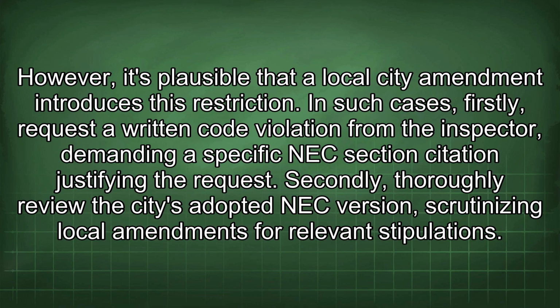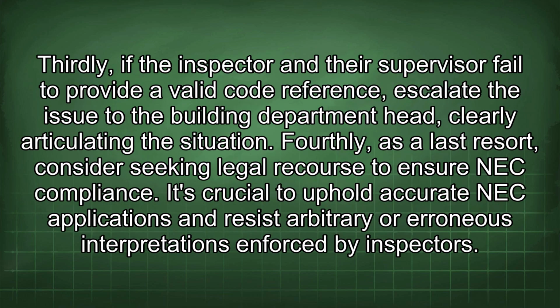In such cases, firstly, request a written code violation from the inspector, demanding a specific NEC section citation justifying the request. Secondly, thoroughly review the city's adopted NEC version, scrutinizing local amendments for relevant stipulations. Thirdly, if the inspector and the supervisor fail to provide a valid code reference, escalate the issue to the building department head, clearly articulating the situation. Fourthly, as a last resort, consider seeking legal recourse to ensure NEC compliance. It's crucial to uphold accurate NEC applications and resist arbitrary or erroneous interpretations enforced by inspectors.